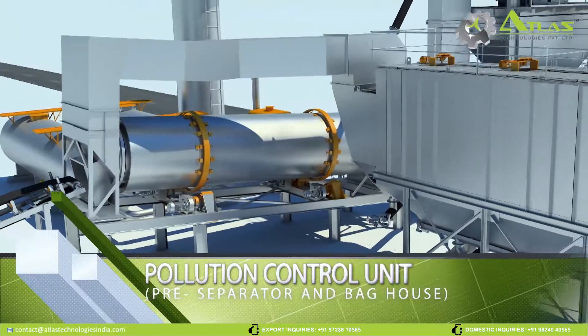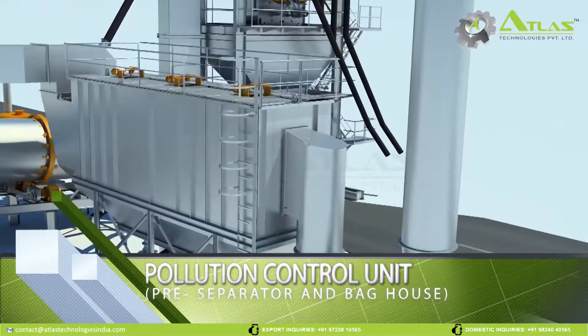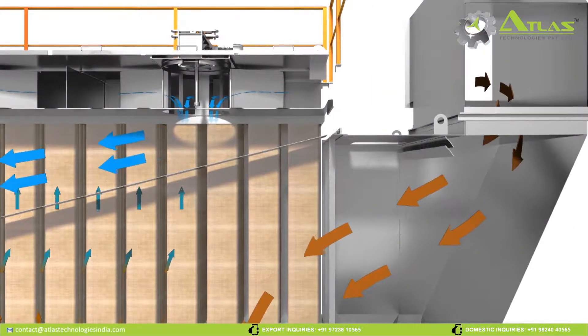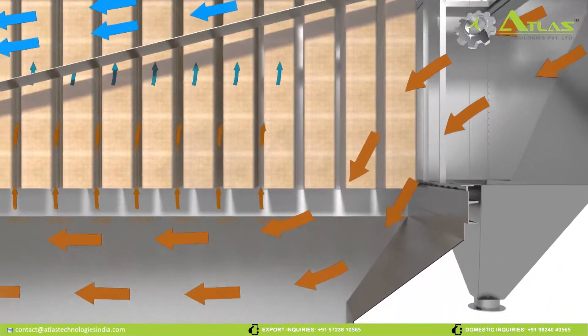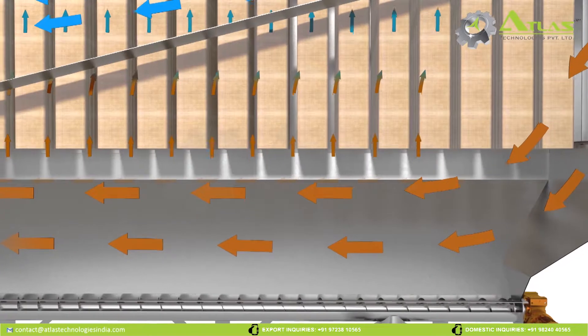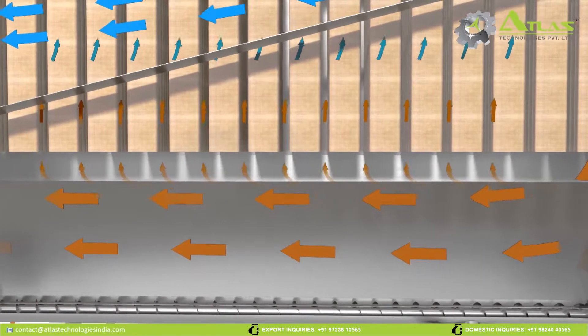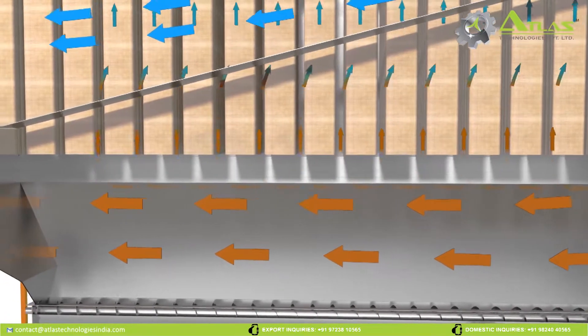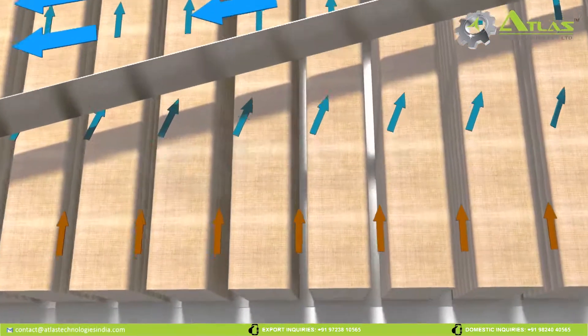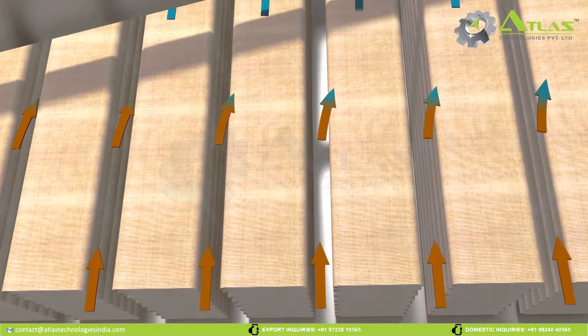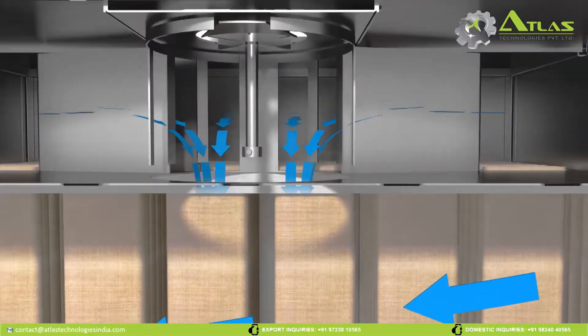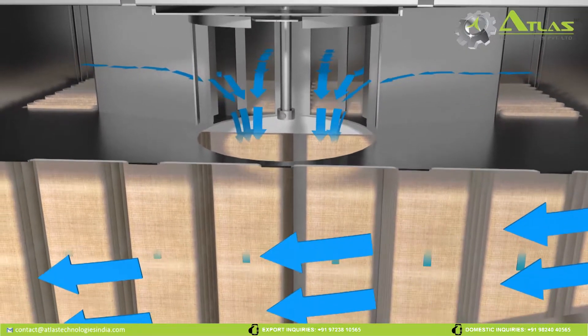Pollution Control Unit. The air along with dust particles enters into the pollution control unit. The heavy particles are separated from air in the pre-separator area. Then it's allowed to pass through series of bags with the help of induced draft system. Fine dust particles will get accumulated on the bag and clean air will pass through the bags and released into the atmosphere.